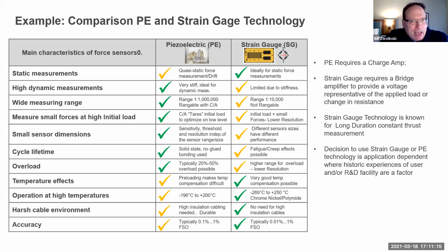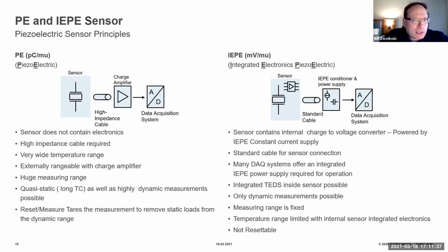It depends on the application, and these check marks can change. That's why it's often so hard to compare. But the main takeaway is that strain gauge is primarily optimized for static and can do some dynamic. Piezoelectric is optimized for dynamic and can do quasi-static. So a little bit more on the terminology. Piezoelectric, IEPE. Piezoelectric means that there's an external device called a charge amp, which converts a charge signal, an electrical signal, into a voltage, plus or minus 10 volts.